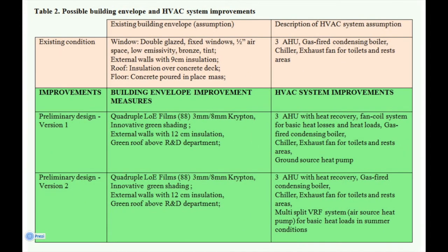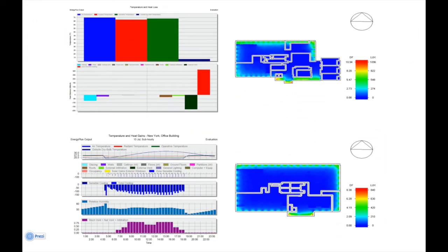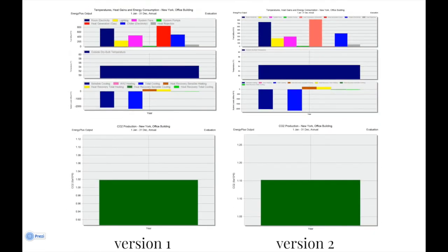Air handling units for clean room and research and development are considered to be packaged type mounted in suspended ceiling. Heating, cooling design, outside dry bulb temperature and daylighting simulation results are the same for both version 1 and version 2 because building envelope preliminary design improvements are the same for both versions. The main aim was to compare results for energy and fuel consumption and CO2 emissions for those two solutions in order to provide a better solution which meets energy conservation requirements of ASHRAE 189.1 and to examine life cycle costs.